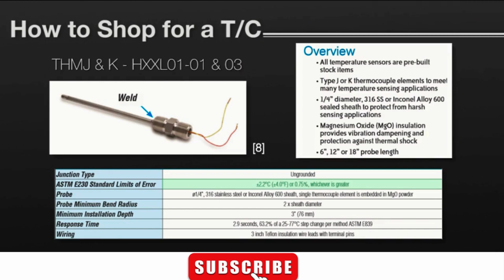This means that at temperatures lower than 293 degrees C, you will always have an error in your reading up to 2.2 degrees C. And above 293 degrees C, your error will be up to that 0.75% of whatever temperature you're actually measuring. If you need to fit the probe into a tight location, you can bend it at a right angle without damaging those internal wires, but you need to make sure that you supply at least a 1/2 inch bend radius, that's a 12 millimeter bend radius. The spec mentions a minimum installation depth of 3 inches, which is 76 millimeters.